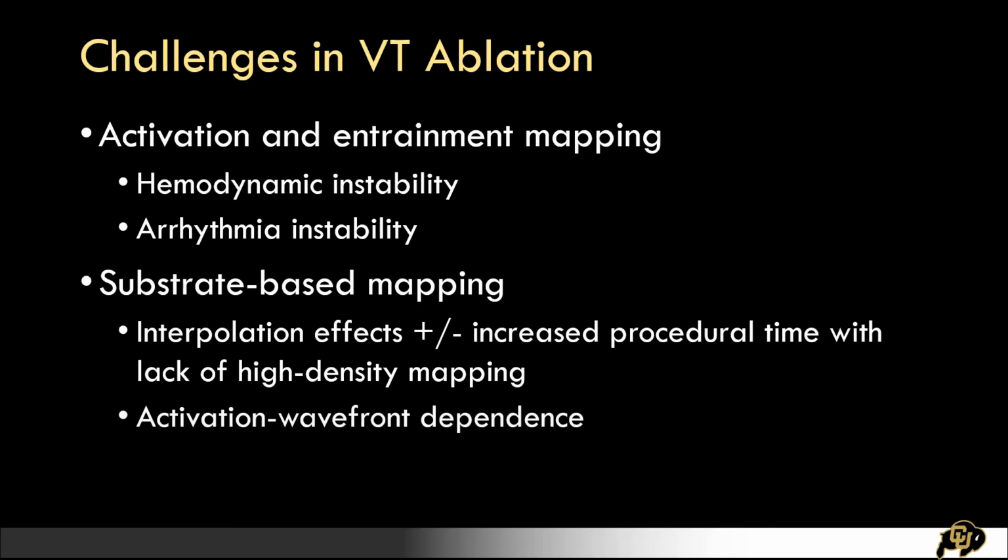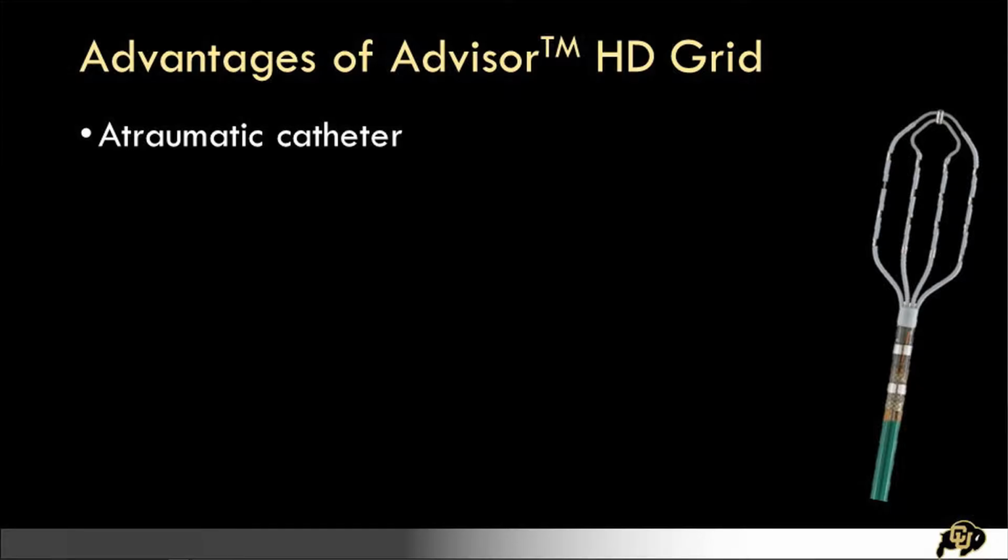And then there's this emerging concept of activation wavefront dependence, with which contemporary or standard methods of substrate mapping are limited. Advantages of the grid are, first of all, it's a very atraumatic catheter. So you can move this all over the place. It bends and conforms to whatever structures it contacts. I can't say it's impossible, but it's very, very close to impossible to perforate with this catheter.